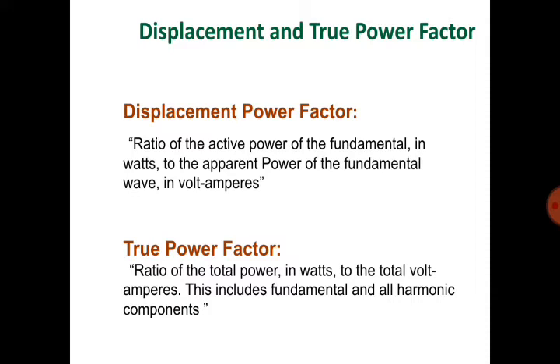Displacement power factor is the ratio of the active power of the fundamental in watts to the apparent power of the fundamental wave in volt-amperes. True power factor is the ratio of the total power in watts to the total volt-amperes — this includes fundamentals and all harmonic components.